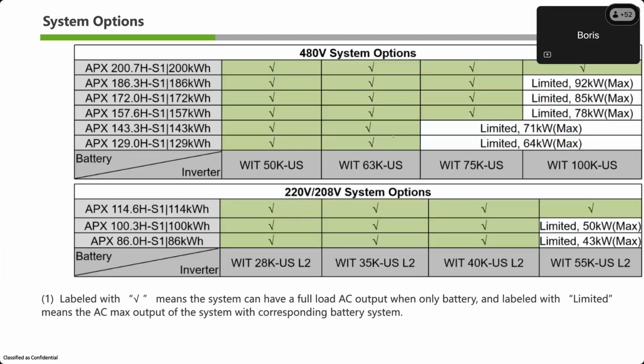I have some charts here to show the configurations of the WIT and APX that are available or optimal. So you'll see that our battery has a max discharge and charge rate of C/2. So on a 100 kilowatt hour battery, the max charge on that is 50 kilowatts. You can still use a smaller battery on a larger inverter, but you'll be limited by the battery C rate only in charging your battery. So we just like to show this for the WIT 100K. If you connect it to an APX 129 kilowatt hour, you'll be limited to 64 kilowatts, but the system will still operate just fine. There's no restriction there except that you have that C/2 rate on the batteries.